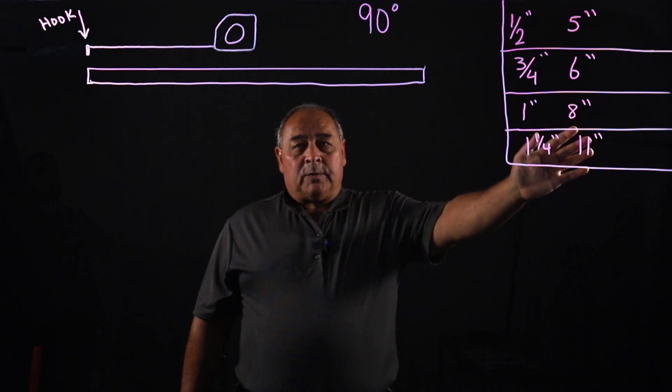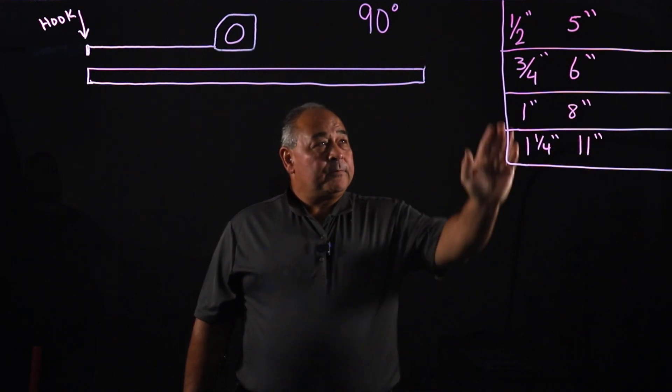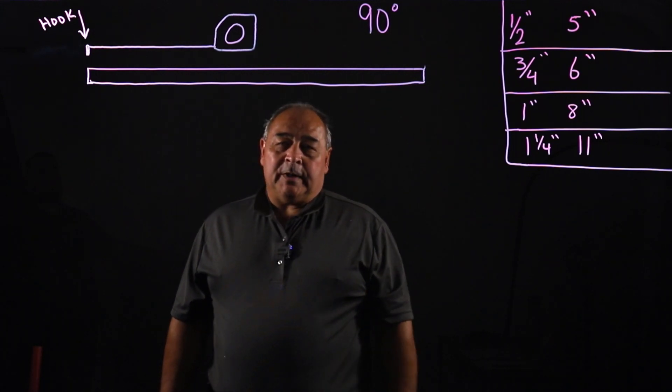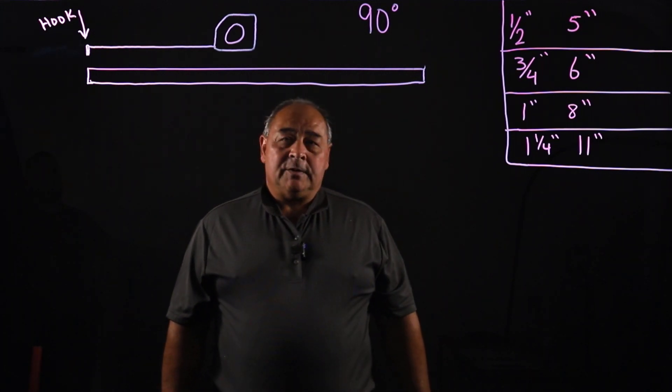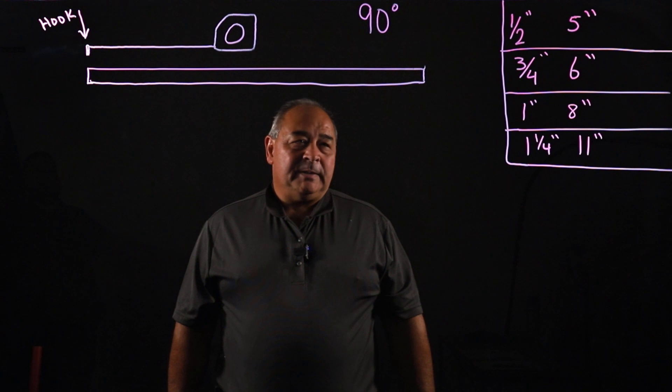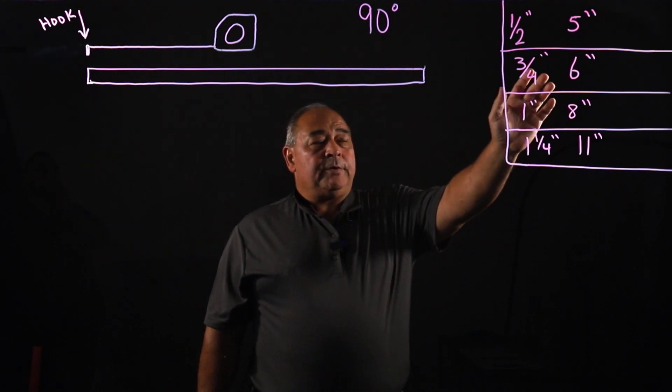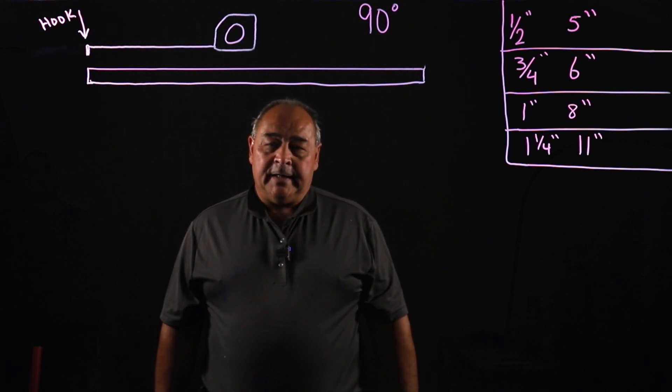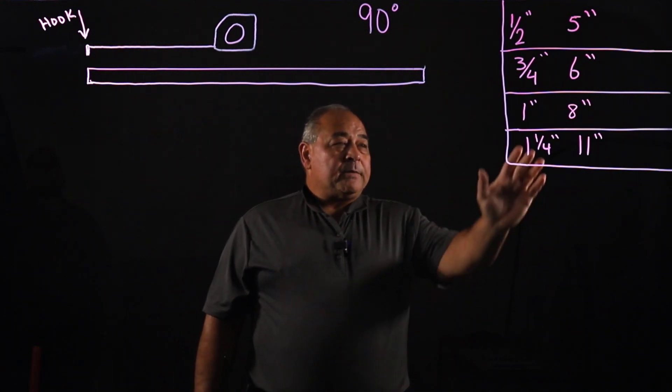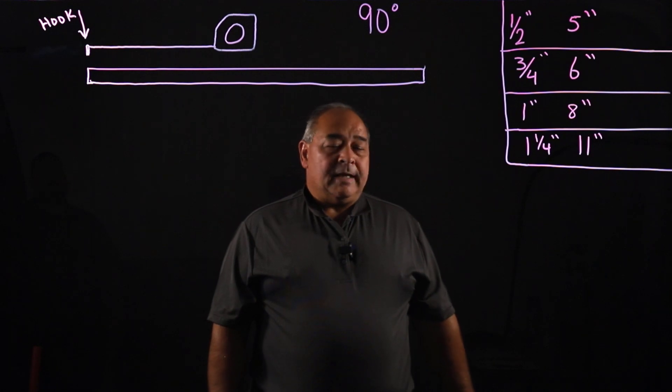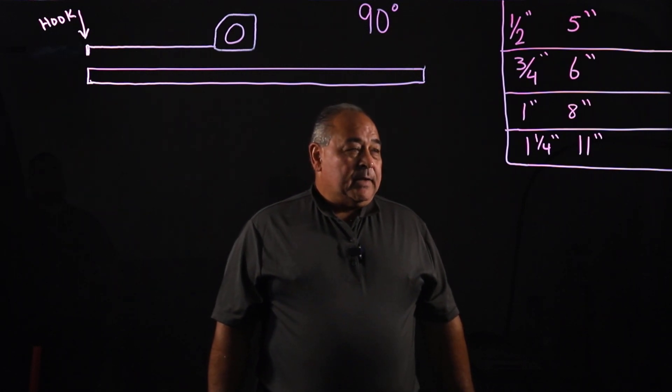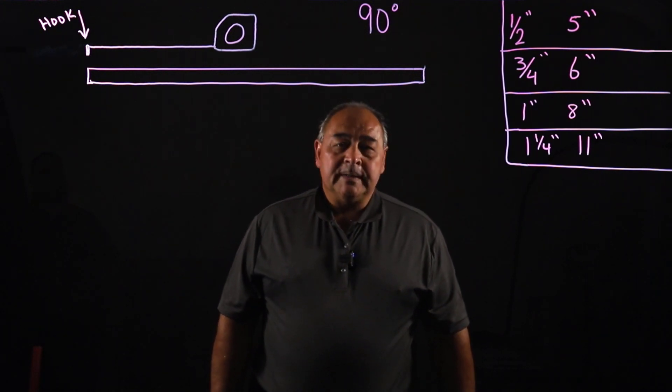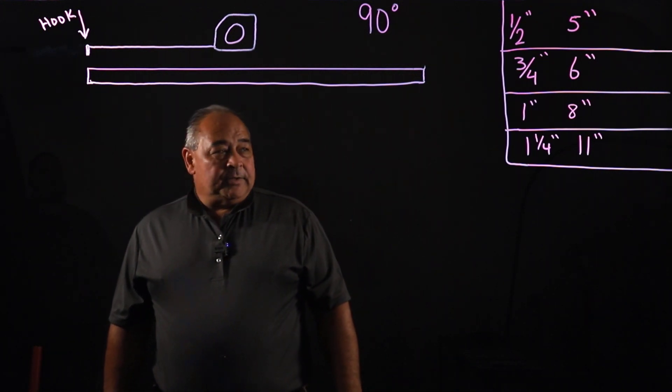The common deductions for hand bending, for half-inch, we've got a five-inch deduction. With Amtech, we rarely deal with half-inch unless we do some specialty control type work. Most of this is going to be referring to three-quarter inch, which is a six-inch deduction for a 90. Sometimes we're dealing with one inch, and it's an eight-inch deduction. Then for some larger conduit, EMT, we might be dealing with inch and a quarter, and that'd be an 11-inch deduction.